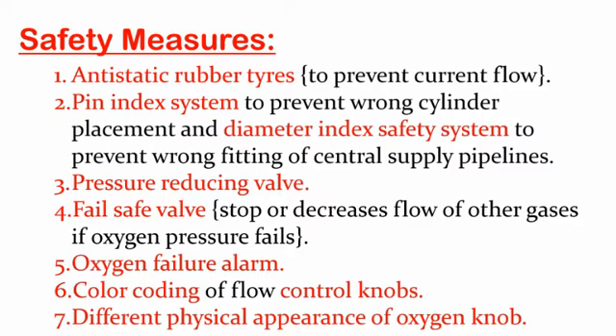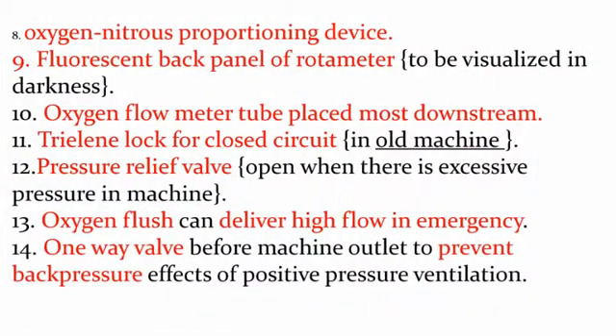There are 14 points for safety measures. The first points include: anti-static rubber tires, pin index and diameter index safety measures, pressure reducing valve, fail-safe valve, oxygen failure alarm, color coding, and different physical appearance of the oxygen knob, nitrous oxide knob, and air knob.